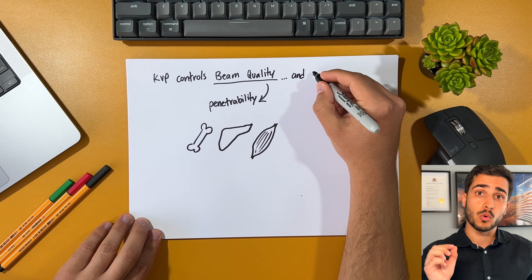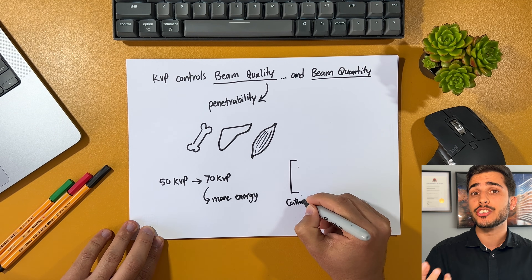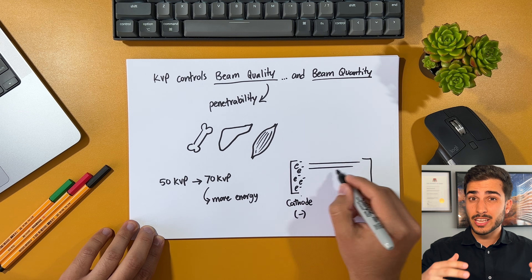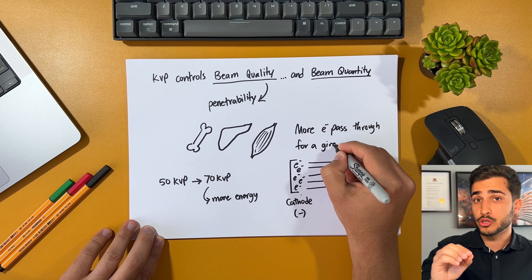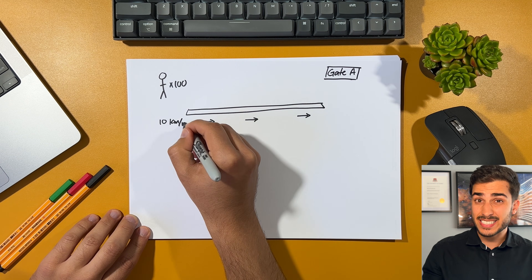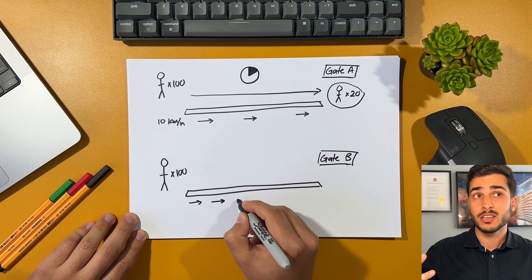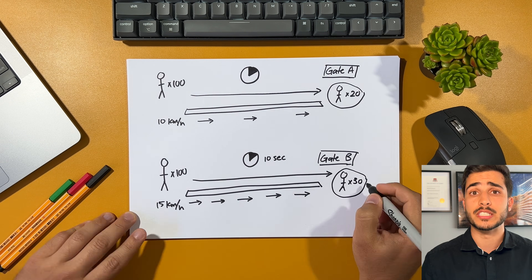Interestingly, KVP also controls the beam quantity. At first it may seem a little odd, but here's an easy way to think about it. For a given MA of 100 and about 50 milliseconds — which equates to 5 MAS — if we increase the KVP from 50 to 70, we've increased the energy of the photons. The more energy the photons have, the more electrons can move from the cathode to the anode in that set exposure of 50 milliseconds. It's like 100 people on a walkway to gate A at 10 km/h — in 10 seconds, only 20 pass the finishing line — whereas the same 100 people on a walkway to gate B at 15 km/h, 30 of them pass the same line. The more electrons passing through in a set time, which equates to how fast they're going and how much energy they have, ultimately results in higher beam quantity. That's how I like to think about it.